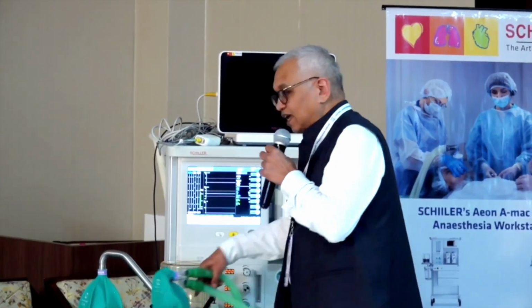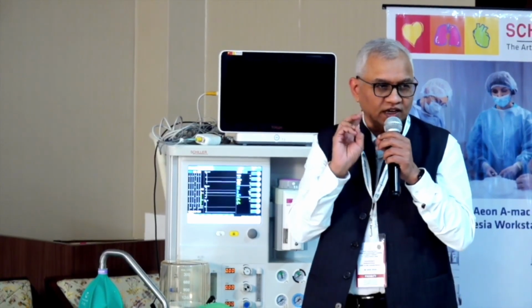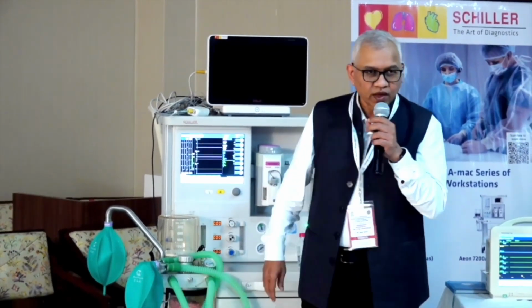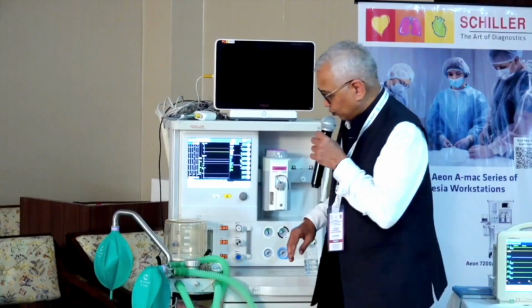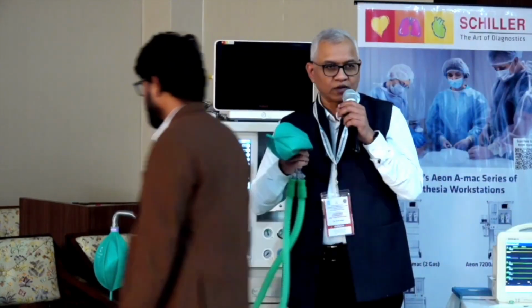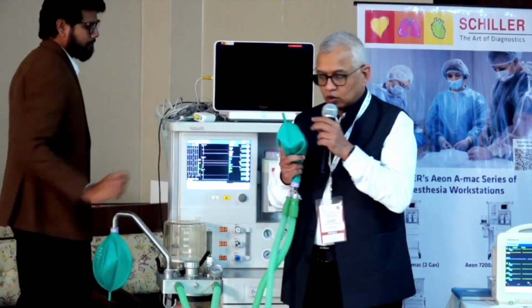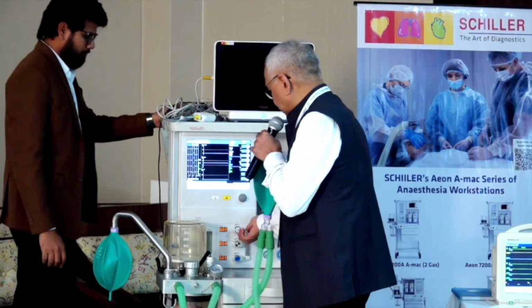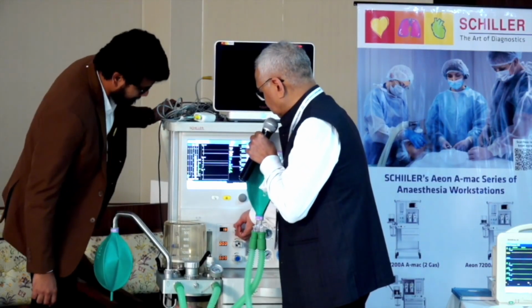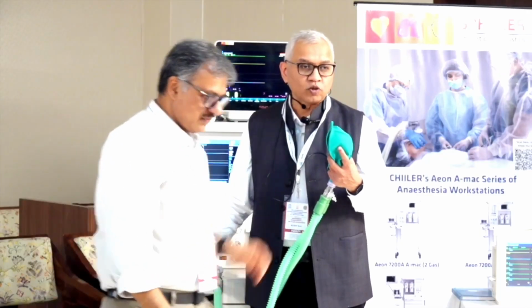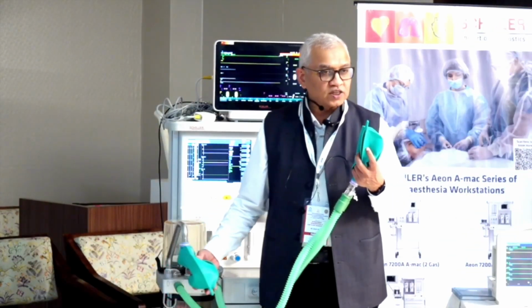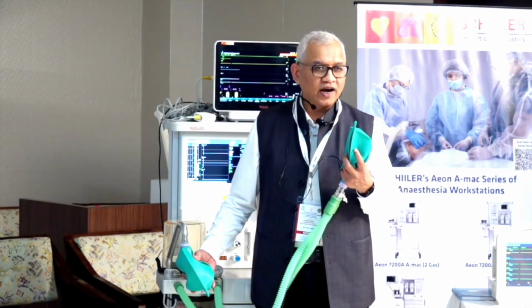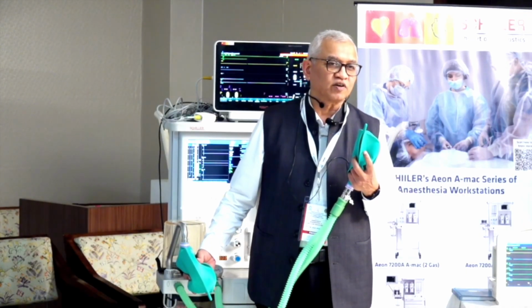Meanwhile, they have done a pre-test and they have identified the leak part, which was not very high. But how to check it manually? For the manual checking, there are two important points. What you need is a two bag. It is called the two bag test. You start the flow at 5 liter. Is the oxygen open? You start the flow at 5 liter. Squeeze both the bags. Now this will help in what? To identify that both unidirectional valves are functioning.